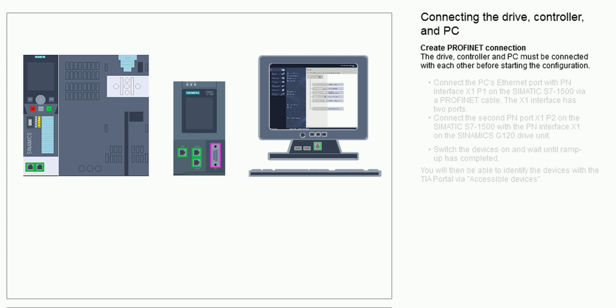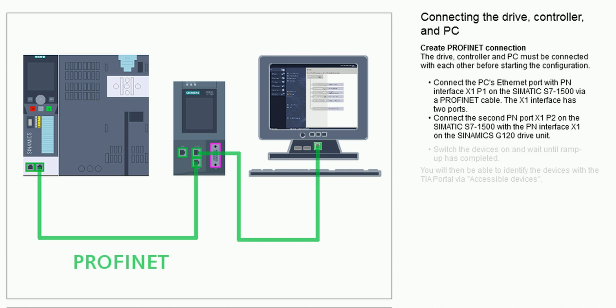Create Profinet connection. The drive, controller and PC must be connected with each other before starting the configuration. Connect the PC's Ethernet port with PN interface X1P1 on the SIMATIC S7-1500 via a Profinet cable. The X1 interface has two ports. Connect the second PN port X1P2 on the SIMATIC S7-1500 with the PN interface X1 on the SINAMICS G120 drive unit.